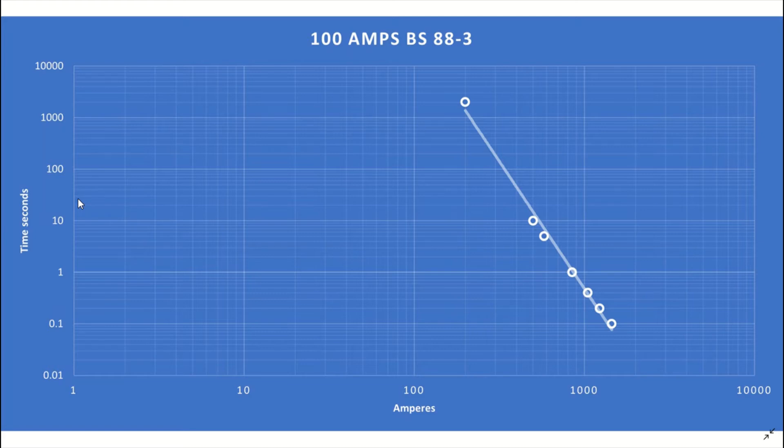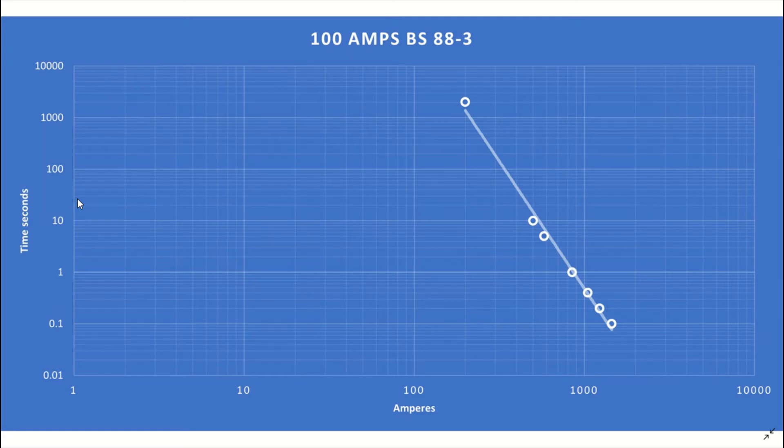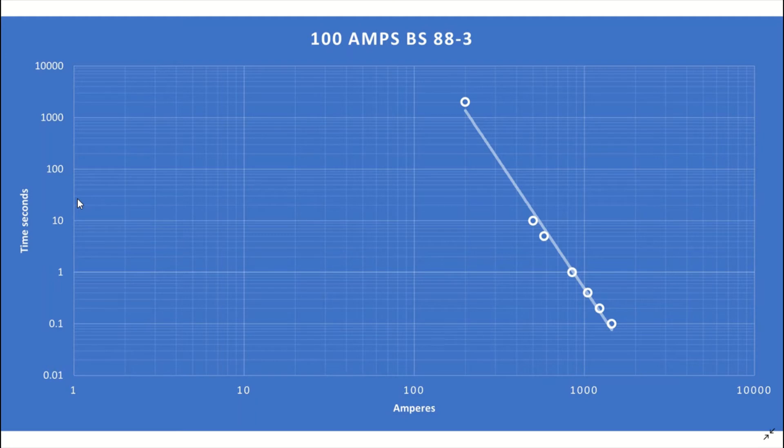This example is for a fuse and you'll notice that the charts for fuses have a steady curve, and for circuit breakers the curve finishes with a vertical straight line which is where instantaneous tripping occurs, which happens when the rating of the breaker is exceeded by a certain number of times which depends on the type of breaker. But in these examples I've used the values for fuses, in this case a BS88-3 fuse.